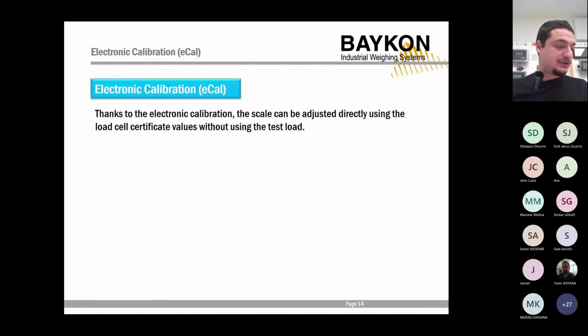Electronic calibration is simply done by writing the certificate values that you have on your load cell, which are, if I'm not wrong, the capacity, the rated output, and the division value of your scale, and by entering those from your device, that's basically it, that's all you got to do. The rest is done by the device itself.